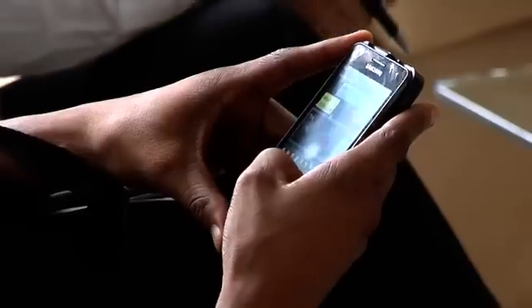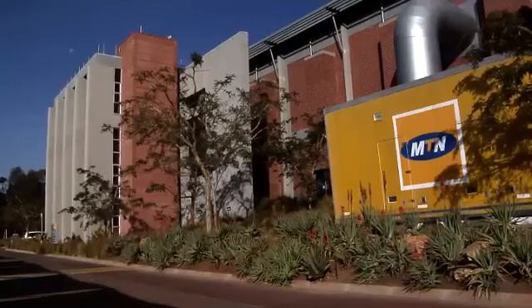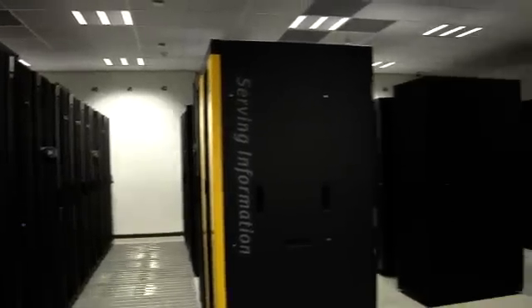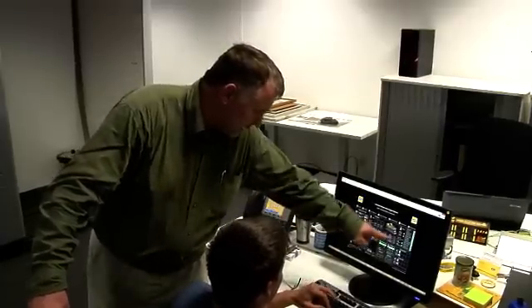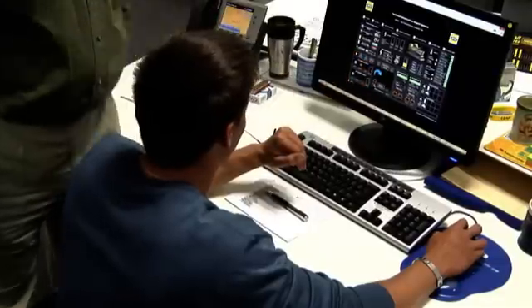Chatting away, SMSing or surfing the net, MTN's data centre in Fairlands heats up quite a bit when dealing with customers' data. If we don't keep it cool, the equipment will overheat and we'll have data loss in the data centre. We try and keep it within ASHRAE class 1 limitations, i.e. 23 to 27 degrees C.